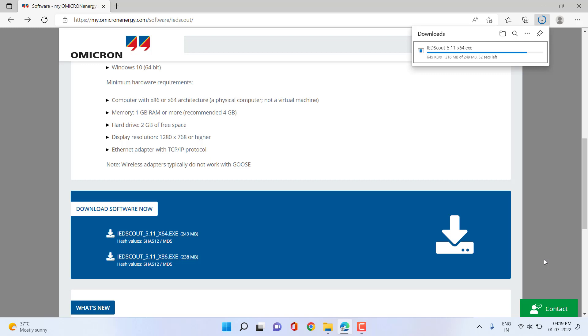If you are a beginner, you can simulate an IED from the simulator section of IEDScout using the localhost IP address. You can enable the loopback adapter as an interface to simulate, and connect the simulated IED from the browser section because IEDScout can be used as both a simulator and a client. Basically, there is built-in support for simulating an IED while also connecting to multiple IEDs in parallel, giving you both functionalities to learn client-server communication.